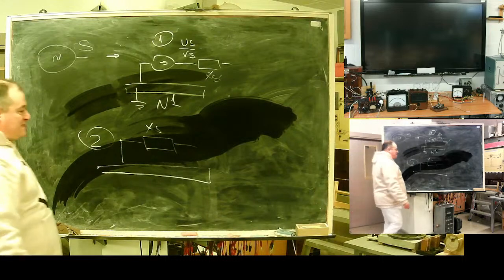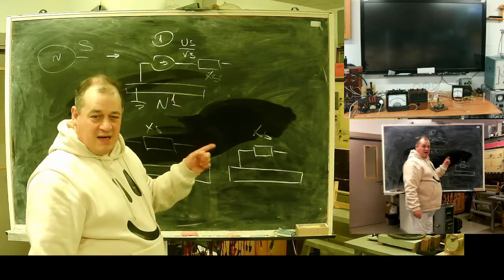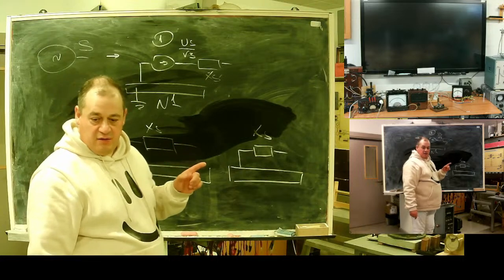For negative sequence, it will be the same system impedance. For zero sequence, approximately X system, but take care. If you have fault calculus data, there may be a difference.